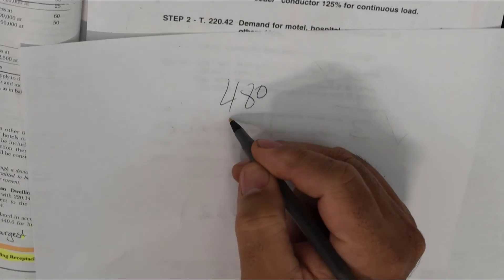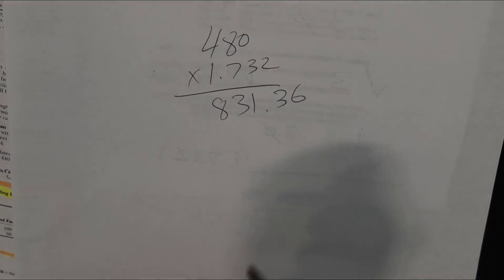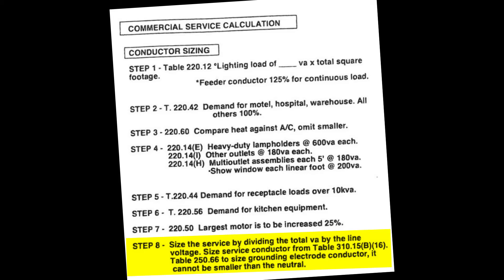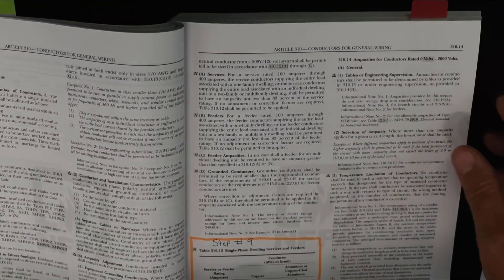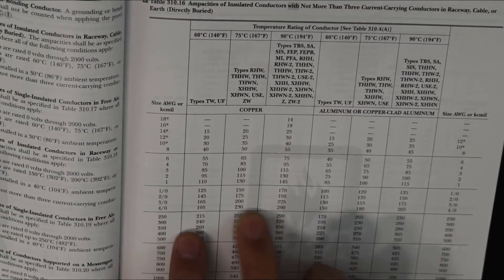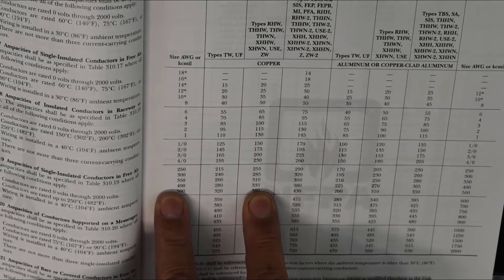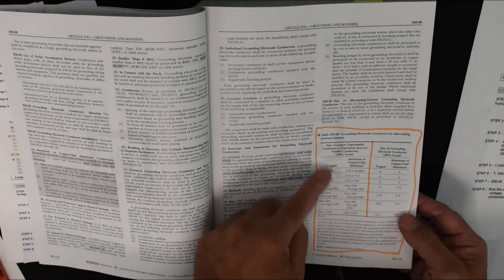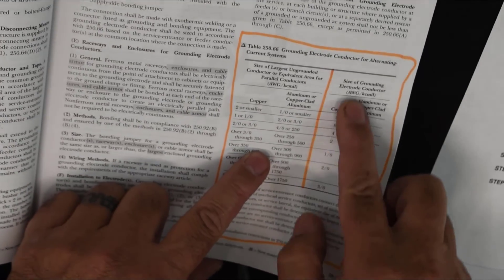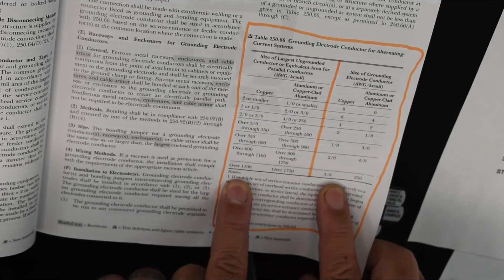For a 480-volt three-phase system, 480 times 1.732 equals 831.36, so you divide your total VA by 831.36. Once you determine the total load in amps, go to Table 310.16 and size the service conductors using the 75-degree Celsius column — whatever ampacity you calculate, that determines the wire size. Once you have the service conductor size, go to 250.66 to determine the grounding electrode conductor size. Note that the largest grounding electrode conductor required by the NEC is a 3/0, applicable when your service conductor exceeds 1,100 kcmil.